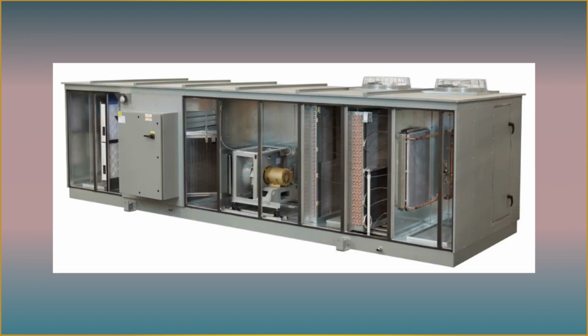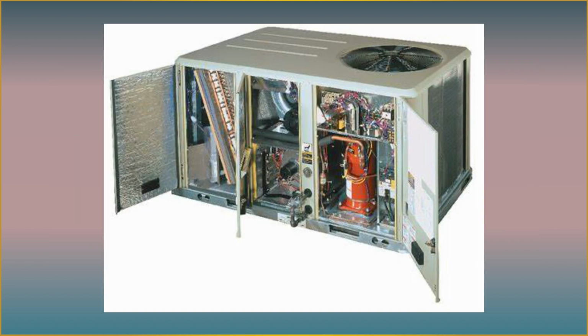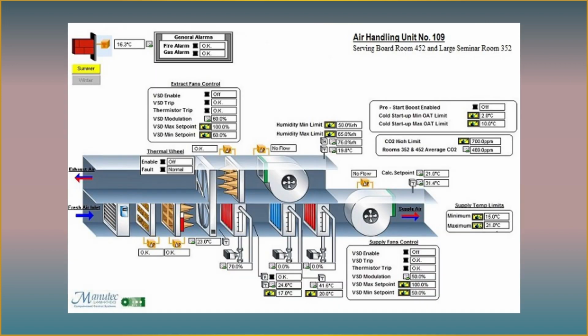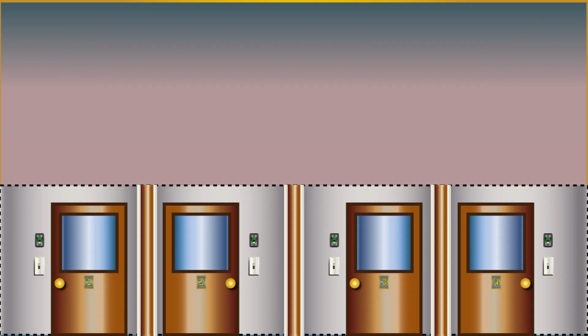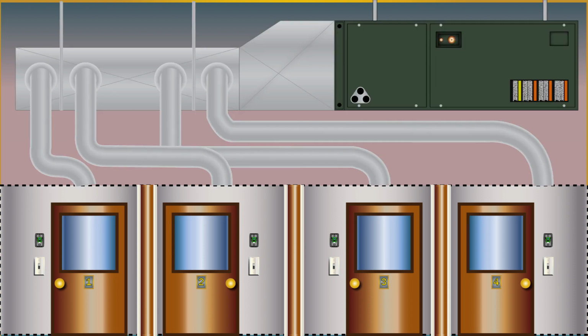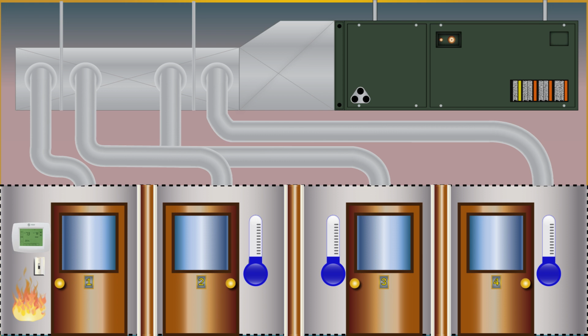This is also how most temperature sensors work in an HVAC unit mounted temperature sensor or temperature sensor in a building automation system controller. They are extremely common. Now that example is just one thermostat with one remote temperature sensor. Now let's say you have a unit that is taking care of a large open area or area with multiple rooms and you have temperature imbalances. Let's say there is one unit taking care of 4 offices, and the office with the thermostat in it is in the corner perimeter, so the temperature is always warmer than that of the other offices on the interior. This will cause the unit to run longer and overcool the other 3 spaces while it tries to satisfy the temperature of the office where the thermostat is located.